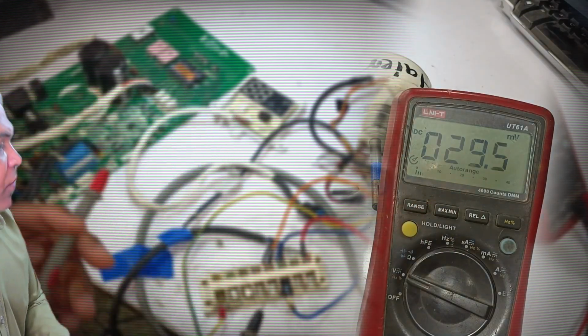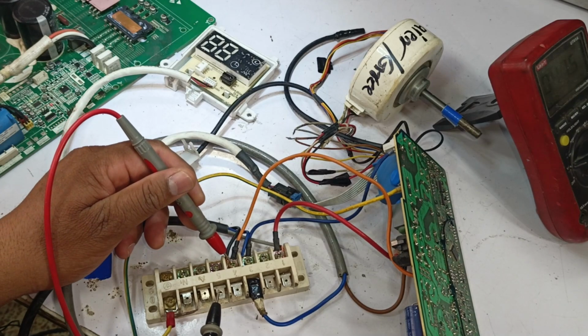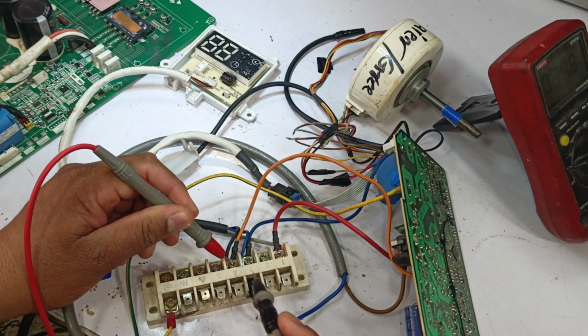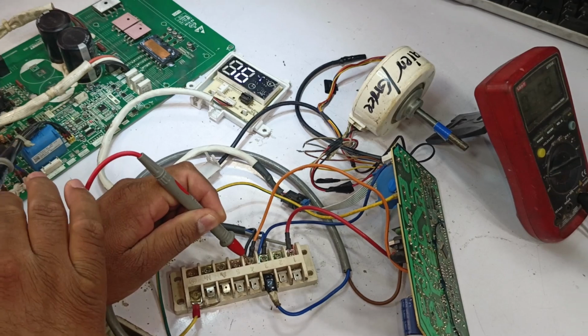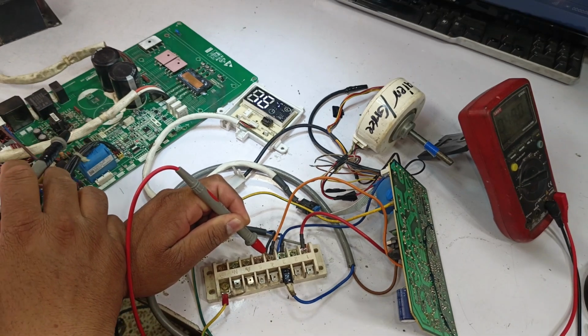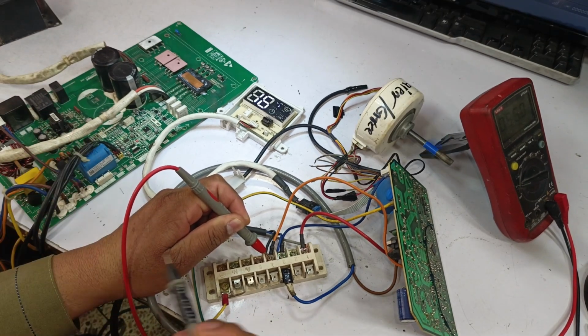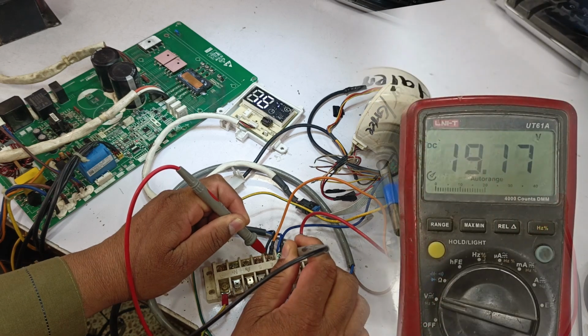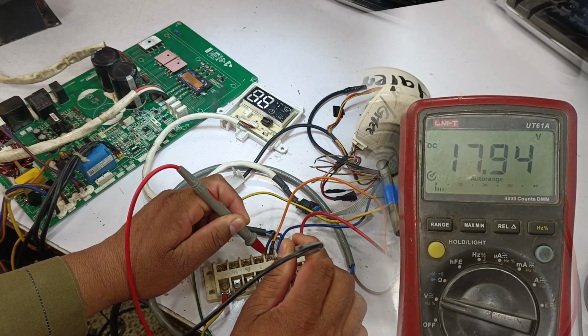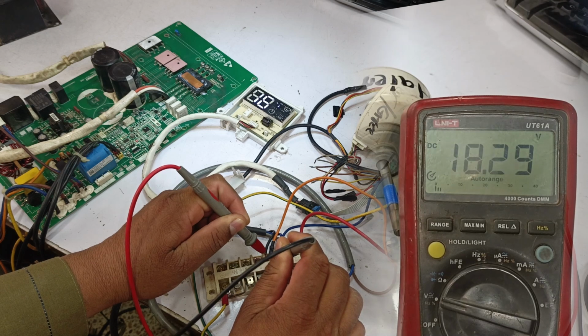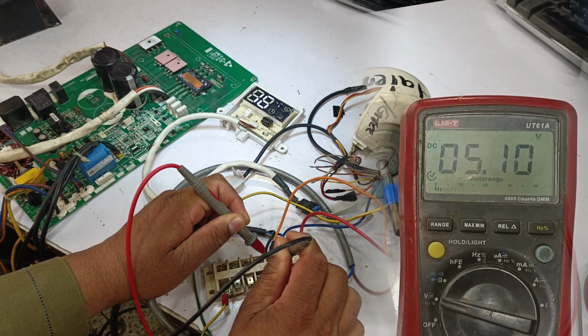The indoor unit has successfully completed switching, but now we need to confirm whether it is properly communicating with the outdoor unit. The multimeter is set to DC voltage mode. Let's connect the probes to the communication and the neutral wire to check the signals. The outdoor unit has started working, and its LED indicators are blinking in a normal pattern. There are fluctuations in the voltage readings, which is a sign that communication is happening. In such cases, when the voltage fluctuates, it generally means the communication is okay.